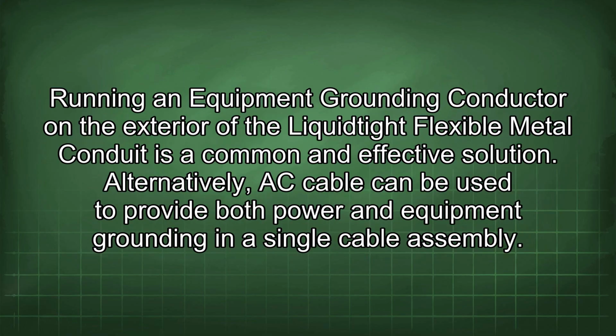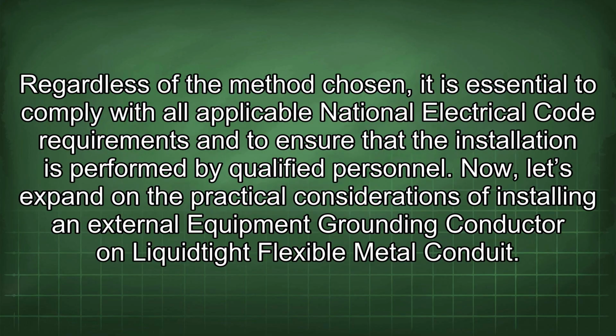Running an equipment grounding conductor on the exterior of the liquid-tight flexible metal conduit is a common and effective solution. Alternatively, AC cable can be used to provide both power and equipment grounding in a single cable assembly. Regardless of the method chosen, it is essential to comply with all applicable National Electrical Code requirements and to ensure that the installation is performed by qualified personnel.